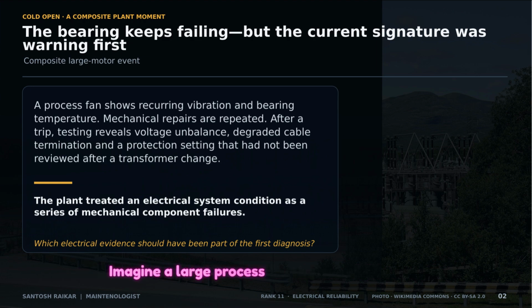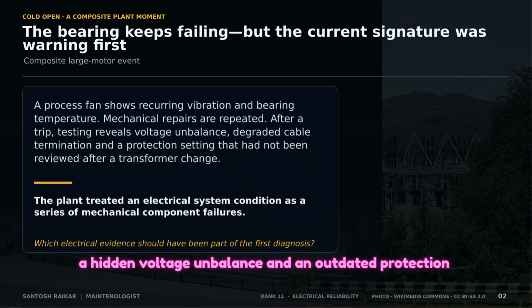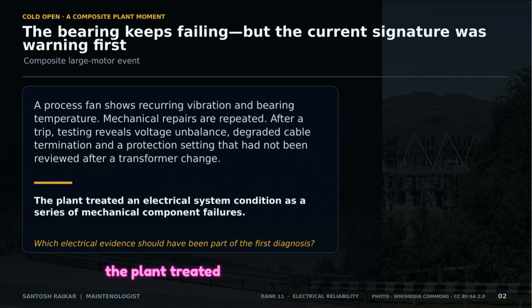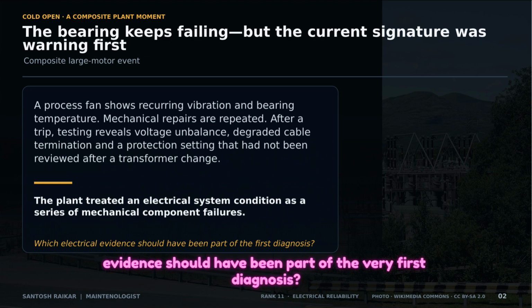Imagine a large process fan where the bearings keep failing despite repeated mechanical repairs. It's only after a major trip that testing reveals a hidden voltage unbalance and an outdated protection setting. In this case, the plant treated a systemic electrical issue as a series of isolated mechanical failures. The question we must ask is, which electrical evidence should have been part of the very first diagnosis?